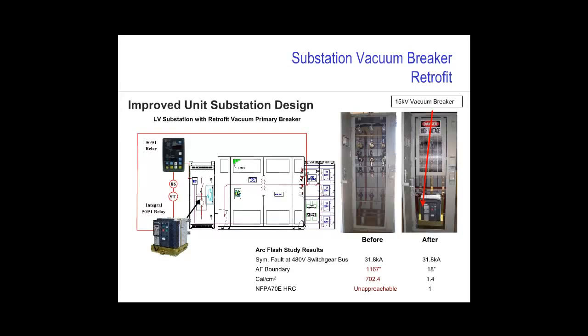Below, I have shown the results of the revised arc flash study in both the before and after scenarios. As you can see, the addition of the vacuum circuit breaker on the primary of this substation greatly reduced the arc flash boundary, the calories per centimeter squared, and the hazard risk category associated with the main secondary bus in this substation. It's interesting to note here, when you look at this diagram, that the integral trip unit in the primary vacuum breaker is actually tripping from secondary current transformers and protecting the secondary bus.